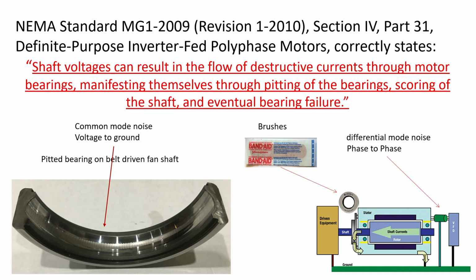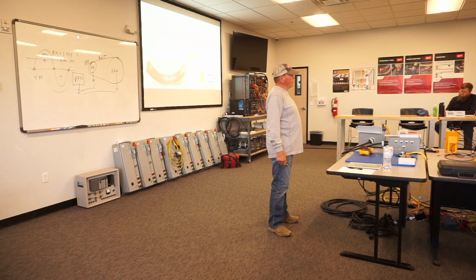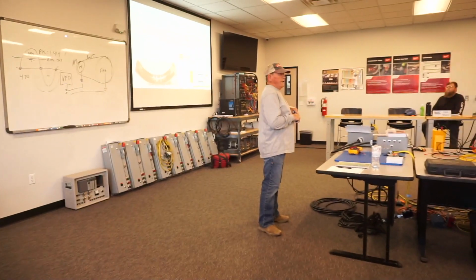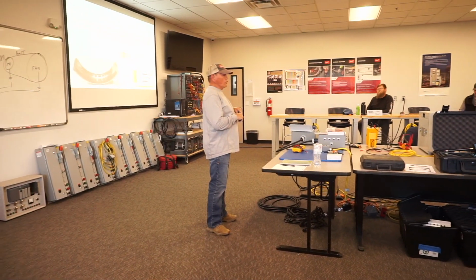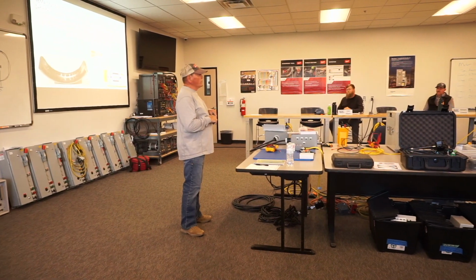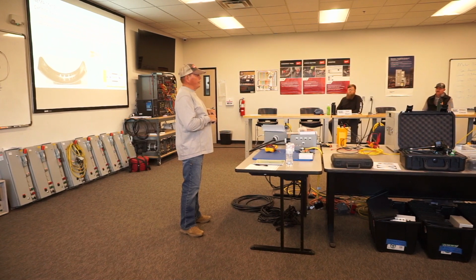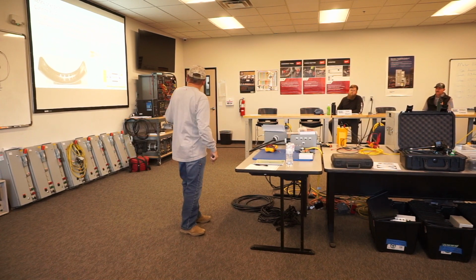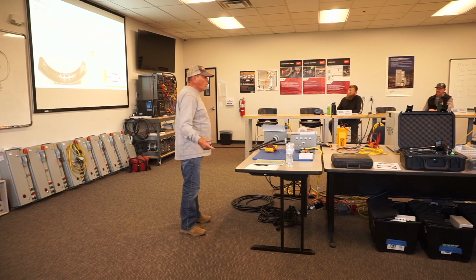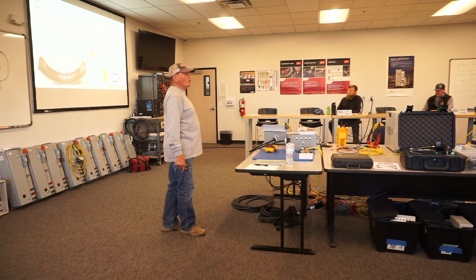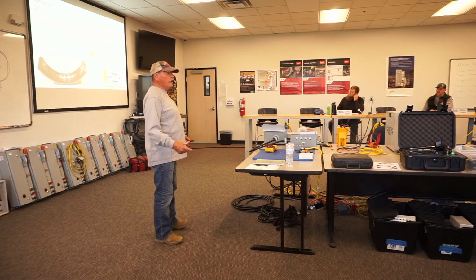I said, well, how long are the brushes gonna last? If that motor's spinning 24/7, and those brushes are riding on that shaft, how long is that? How long before those little fibers don't work no more? And then the next thing you know, you burn out a bearing. Oh, I guess I gotta replace that. I guess I gotta replace that again. I said, why don't you fix the problem? So everybody's got a Band-Aid for everything in our industry right now.